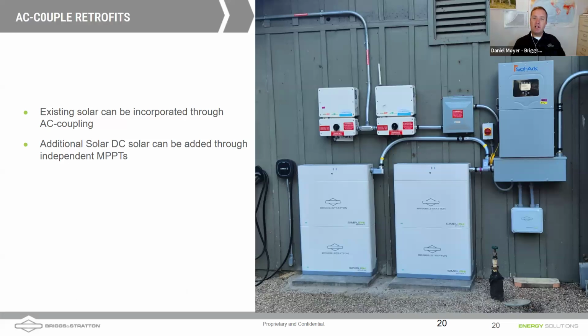Promise I'll show you some SolarEdge. First off, I'm pretty surprised that these solar inverters are still even operating, but they are. Up top on the roof, where this conduit is going, you can see your PV label stickers here. There's modules, there's optimizers. We're sending that DC down the roof. These two inverters are turning that DC to AC. We're landing in a combiner here.